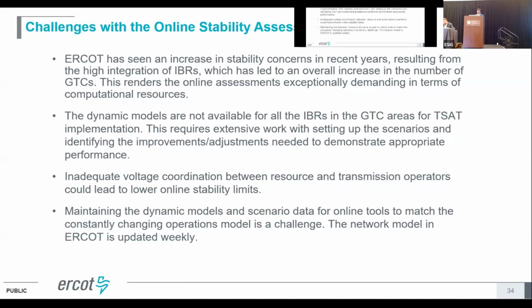We had extensive conversations with both the transmission owners and resource operators to see if there's anything they can do better. Because if a unit is producing MVArs to maintain the voltage at the POI, but the transmission owner also has a reactor connected maybe one station away, then not all the reactive output from the unit is really helping the grid or helping maintain its stability.